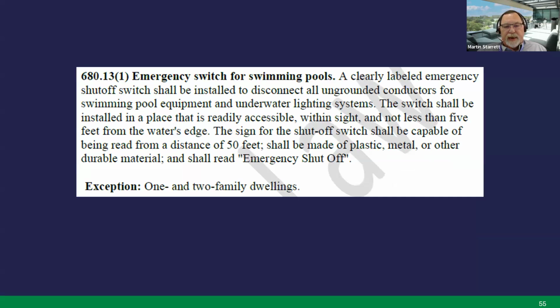Number 3 on the technical amendments is 680.13.1, the emergency switch for swimming pools. In other than one- and two-family dwellings, you're required to have a clearly labeled emergency shutoff switch to disconnect all ungrounded conductors for swimming pool equipment, and a lot of electricians miss this, underwater lighting systems. It's got to be installed in a place that's readily accessible and in sight and not less than 5 feet from the water's edge. You're also required to have signage capable of being read from 50 feet, with the words emergency shut off. Next slide, please.